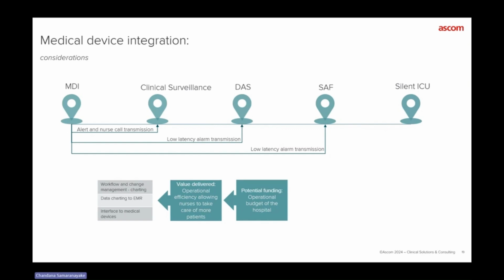As soon as the data comes in, there's a sniffer that identifies this is an alarm and sends it through a low latency priority pathway to the alert manager. This reduces the latency, because if you wait until data packets are built up, keep in mind, for an electronic charting system, the data doesn't need to be real time.